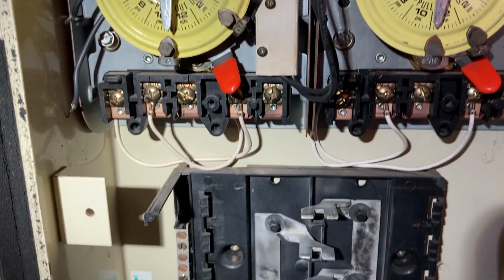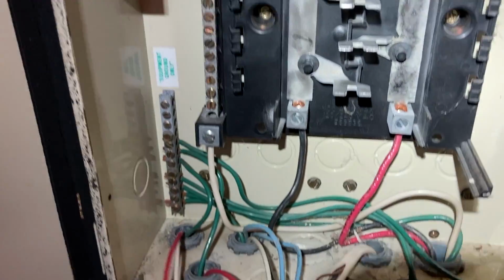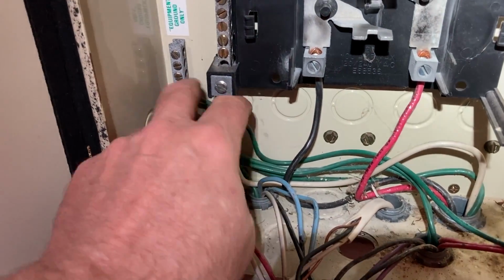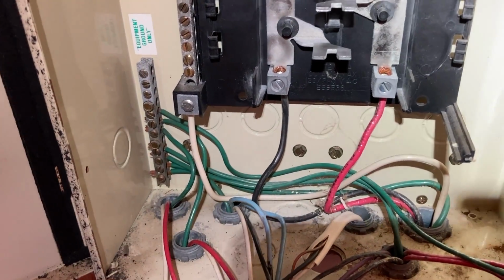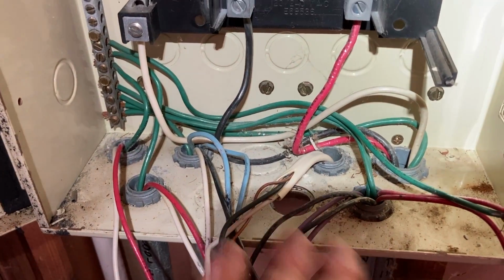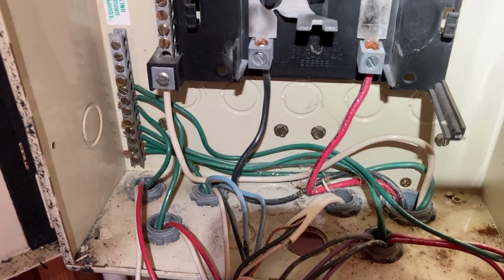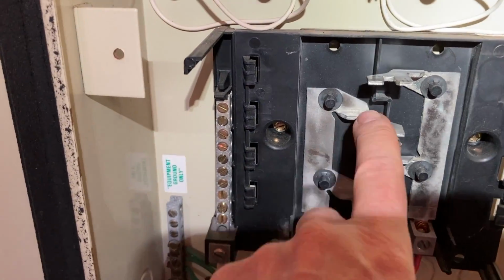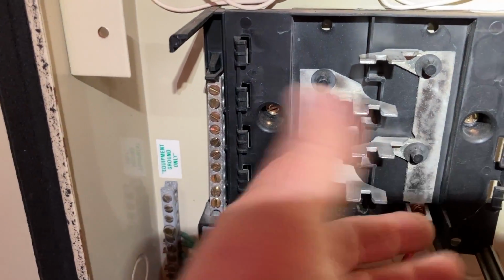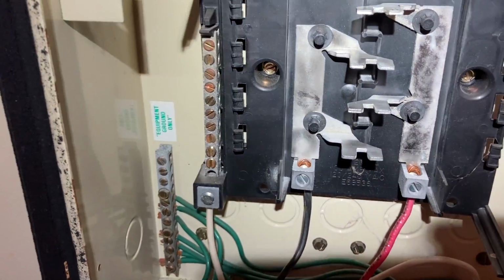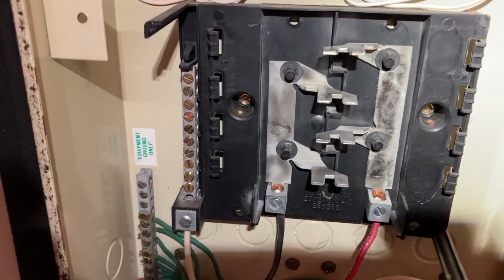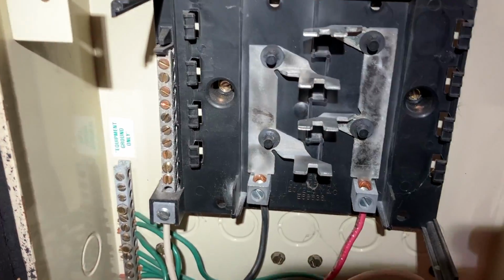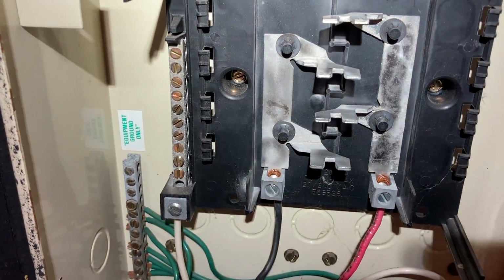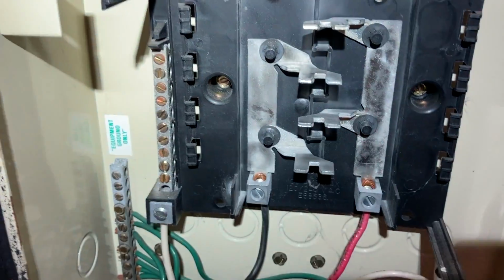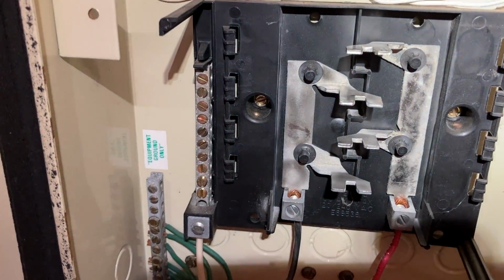So everything's cleaned out now, and you can see what wires are coming up through what conduits. I'm going to leave the grounds back there because they're okay, but now hopefully we can put this back together a little neater. I took a wire brush on the Dremel and buffed the bus contacts off because they had a bunch of crusty pool house dust and corrosion on them. Not too bad, just surface stuff, but hopefully we'll get a better contact on these tangs now.